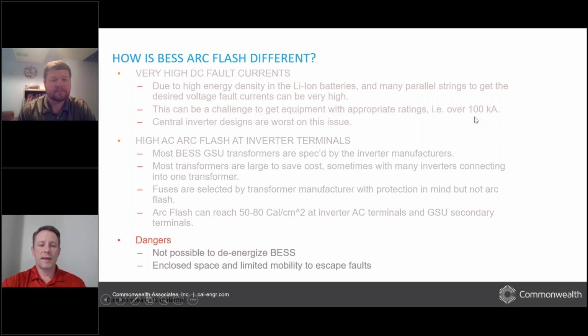The other issue with lithium batteries is if you de-energize them, if you discharge them past a certain amount, I don't remember exactly what that is, maybe 20%, it ruins them. So you really can never work on these systems de-energized. It's also very low mobility because it'll be a lot of batteries inside. It resembles a shipping container a lot of the time, and there's just no escape if you're in there with it. So we try to take that into account when we do our studies.